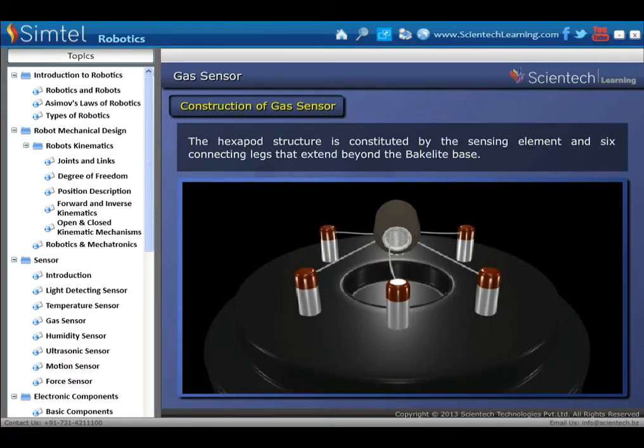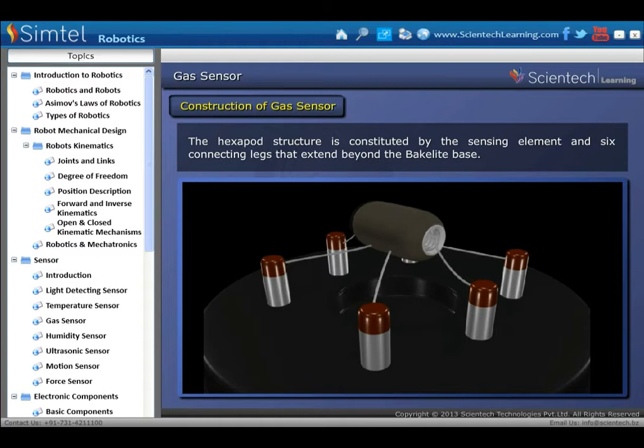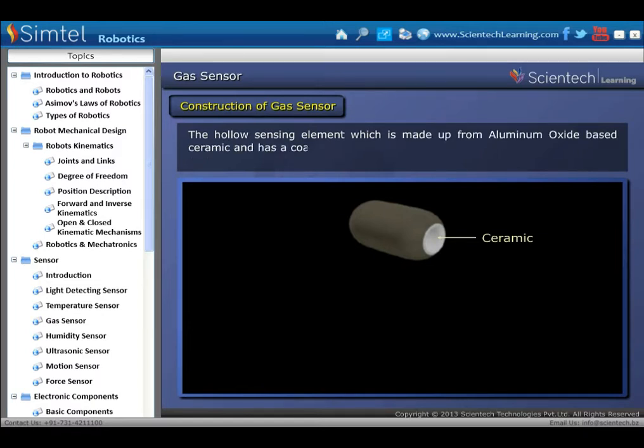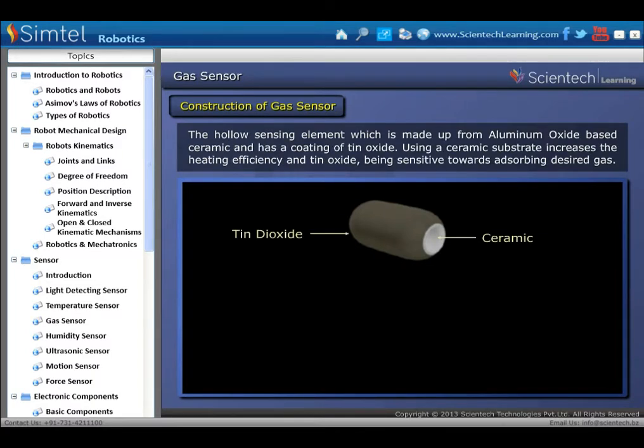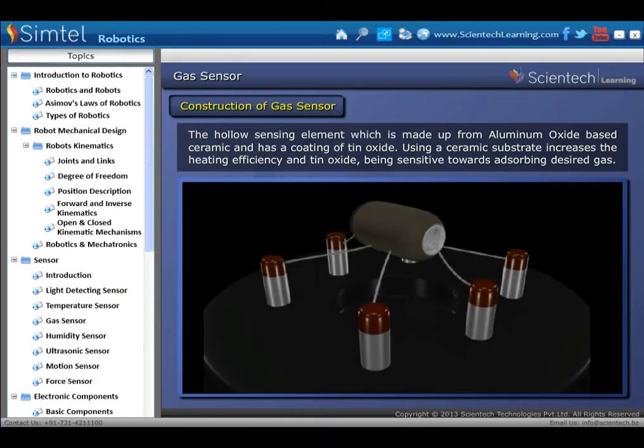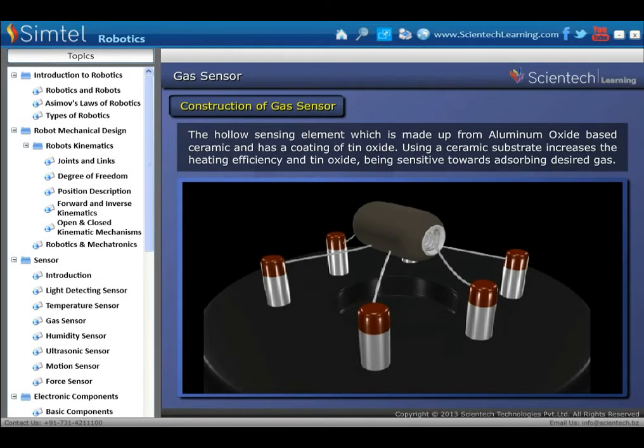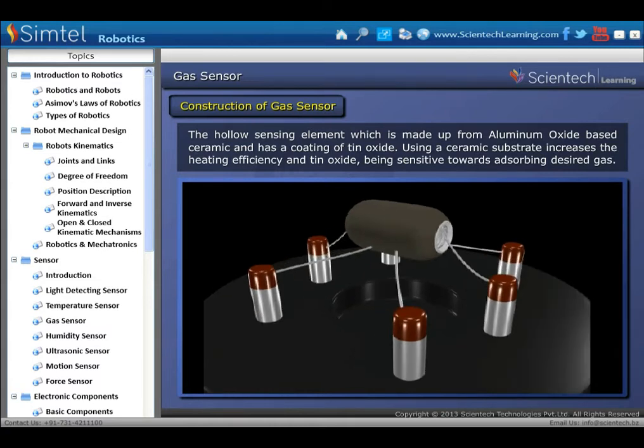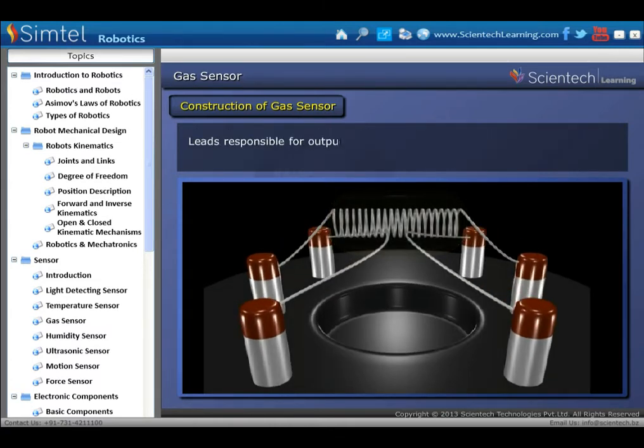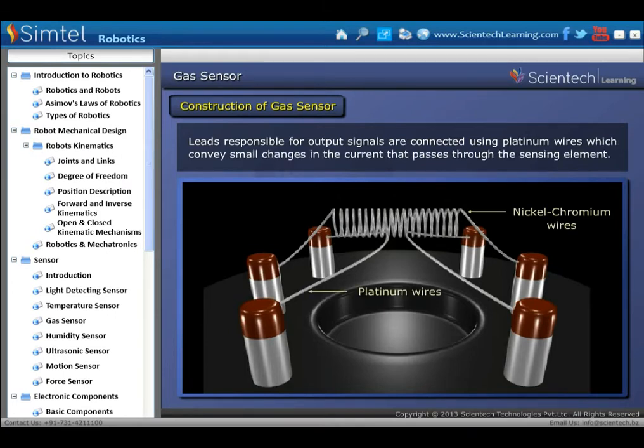The hexapod structure is constituted by the sensing element and six connecting legs that extend beyond the bakelite base. The hollow sensing element, made from aluminium oxide-based ceramic, has a coating of tin oxide. Using a ceramic substrate increases the heating efficiency, and tin oxide is sensitive towards absorbing the desired gas. Leads responsible for output signals are connected using platinum wires, which convey small changes in the current that passes through the sensing element.